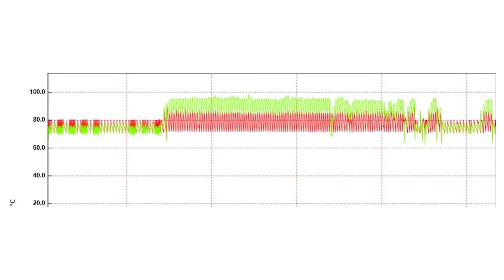We then move into the centre area where quite clearly there's a lot of problems, where actually the return temperatures are higher than the flow temperatures. That clearly indicates a problem, and what was happening was that the control system wasn't actually letting the heat go from the boiler through into the building itself.